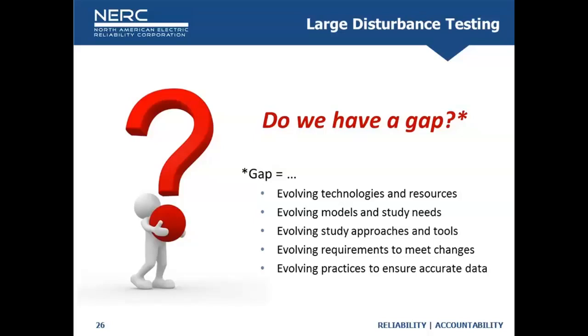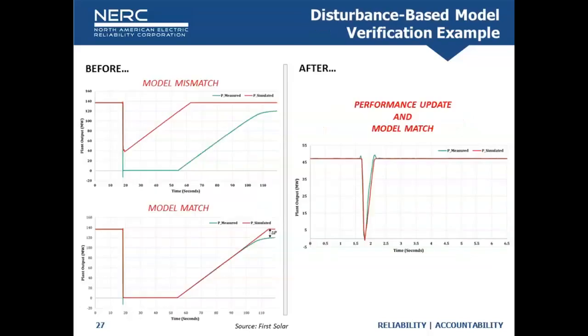We've seen this at the NERC level, and I'll talk about why we're coming on so strongly now, because we're seeing that the vast majority of particularly solar PV resources connected to the bulk power system do not have models that accurately represent reality. There's compliance risk there, but more importantly there's reliability risk. For those familiar with history, that's one of the causes of the 1996 disturbances. The model said everything was great, and in reality it wasn't. We're in that same realm right now, just looking and feeling different. We have models that don't accurately represent reality, and addressing that risk is a very high priority right now, particularly for interconnection-wide studies.